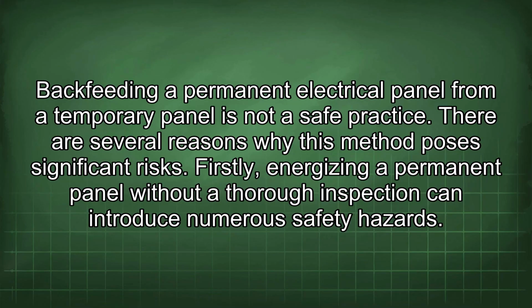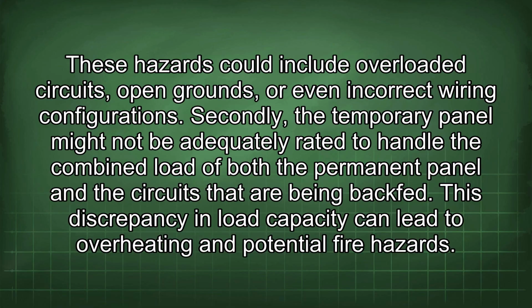Backfeeding a permanent electrical panel from a temporary panel is not a safe practice. There are several reasons why this method poses significant risks. Firstly, energizing a permanent panel without thorough inspection can introduce numerous safety hazards. These hazards could include overloaded circuits, open grounds, or even incorrect wiring configurations.